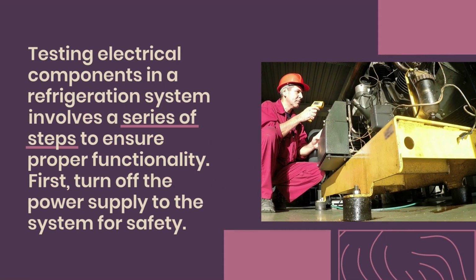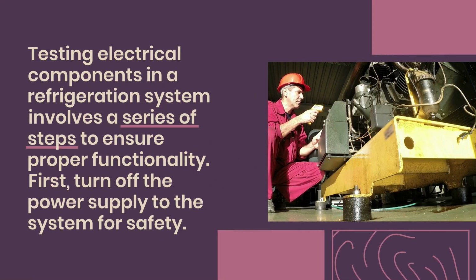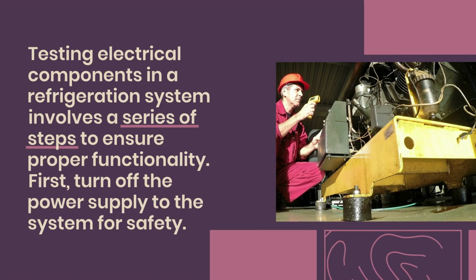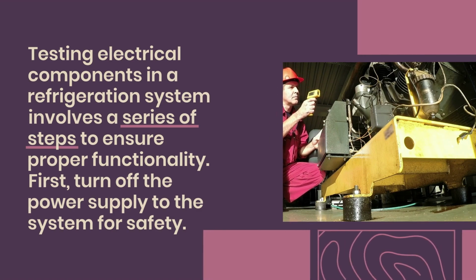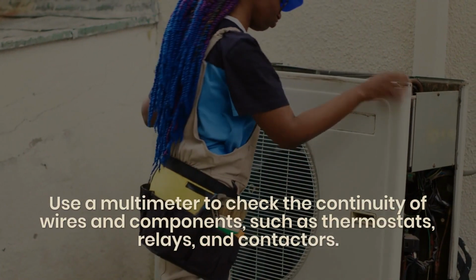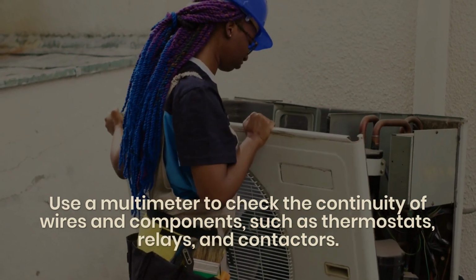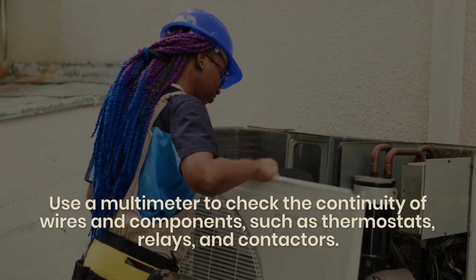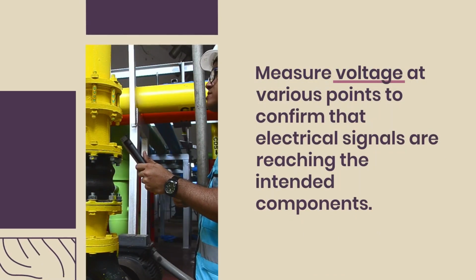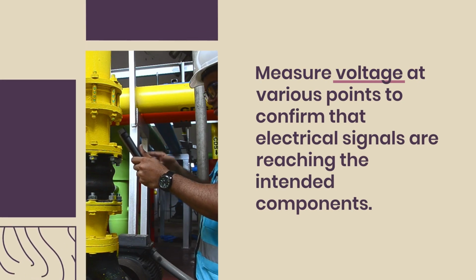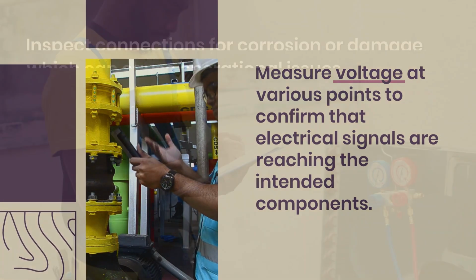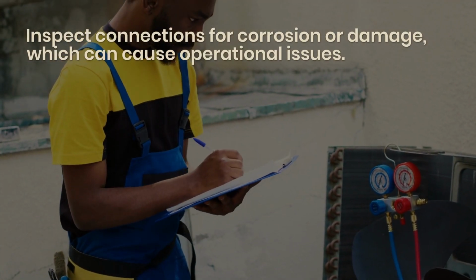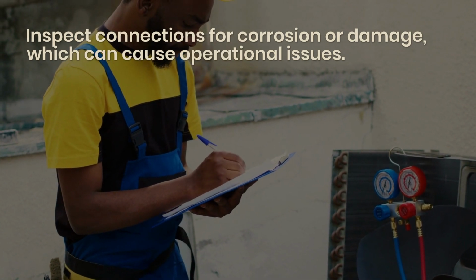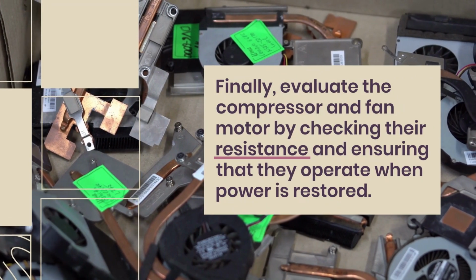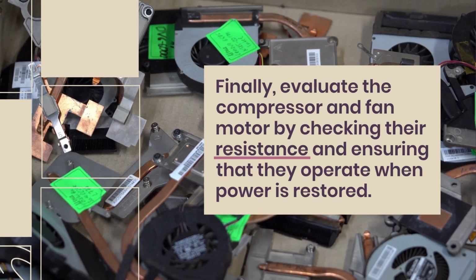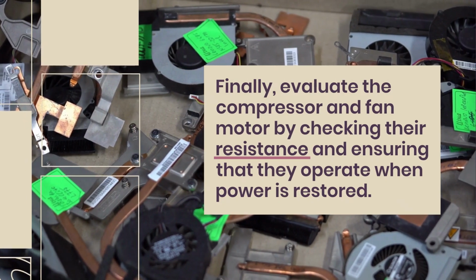12. How do you test electrical components in a refrigeration system? Testing electrical components in a refrigeration system involves a series of steps to ensure proper functionality. First, turn off the power supply to the system for safety. Use a multimeter to check the continuity of wires and components, such as thermostats, relays, and contactors. Measure voltage at various points to confirm that electrical signals are reaching the intended components. Inspect connections for corrosion or damage, which can cause operational issues. Finally, evaluate the compressor and fan motor by checking their resistance and ensuring that they operate when power is restored.